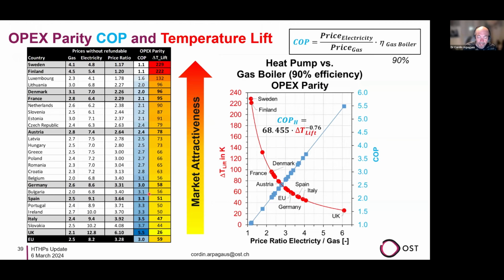This is just showing the link between the price ratio and the COP. If you look at the red curve, as the price ratio gets smaller, so electricity gets cheaper, then the economic temperature lift for the heat pump gets larger. With a ratio of 2.5, an 80 Kelvin lift is still economic compared to a gas boiler from an operating point of view - the costs are at parity.